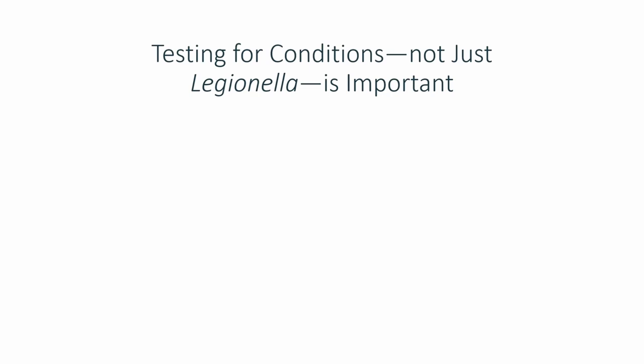I think it's a good idea to test for Legionella because the data is very useful, but you have to understand the limitations. One limitation is that a Legionella test will not tell you exactly what factors contributed to it. So if you get unacceptable test results, you don't know exactly what it was. Do you have inadequate temperatures? Inadequate disinfectants? Is it water age? What is the problem?